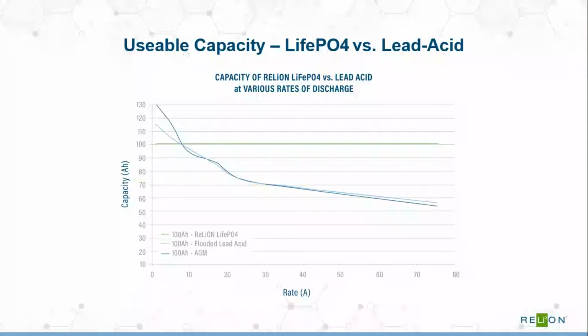And I say 100 amp hours nominal because the flooded lead acid battery is actually rated at 115 amp hours and the AGM is rated at 130 amp hours. And that's because the rate at which the capacity diminishes as the discharge rate increases. So on our y-axis here, we have capacity in amp hours, and our x-axis, we have the rate of discharge.